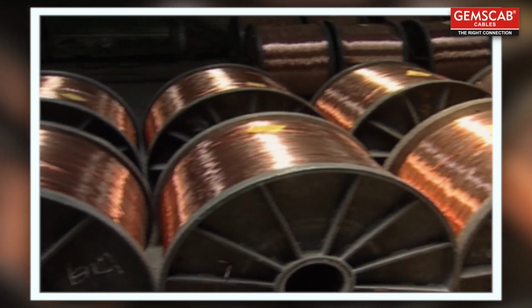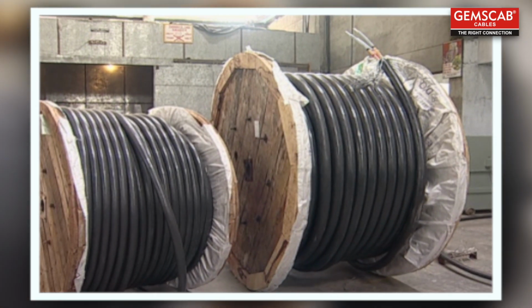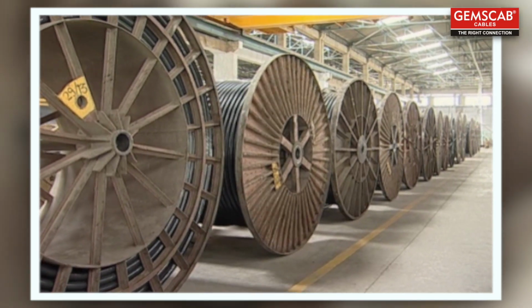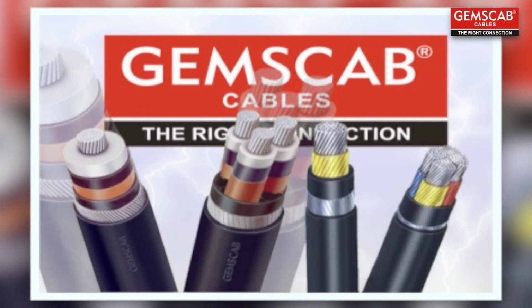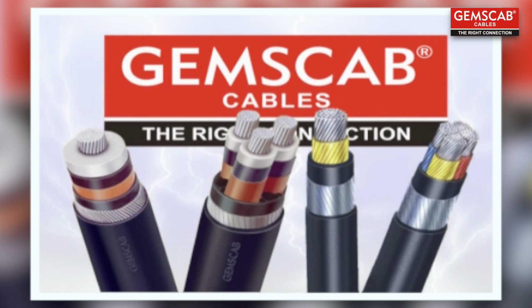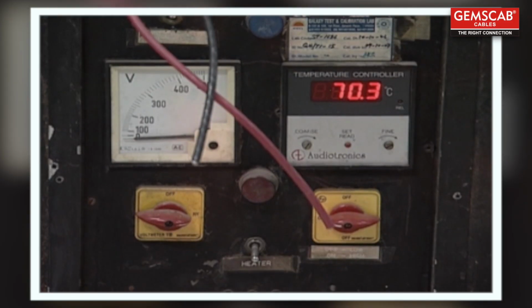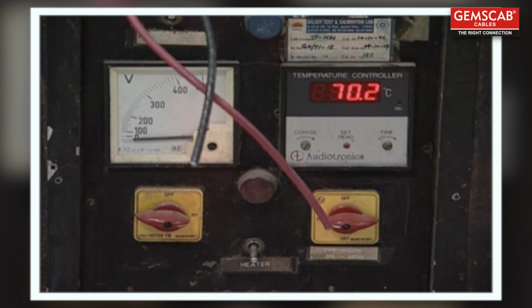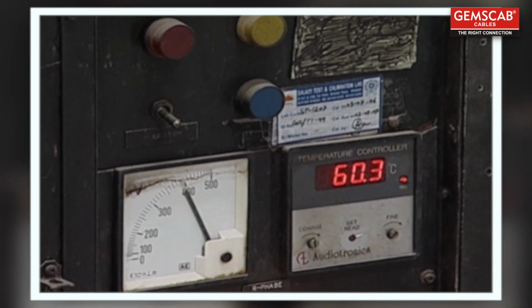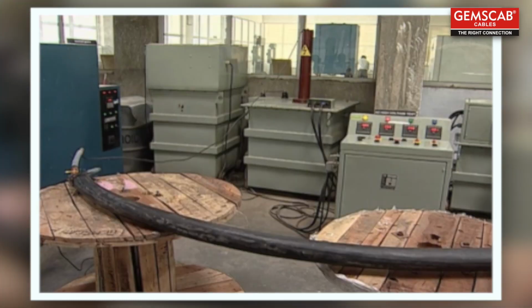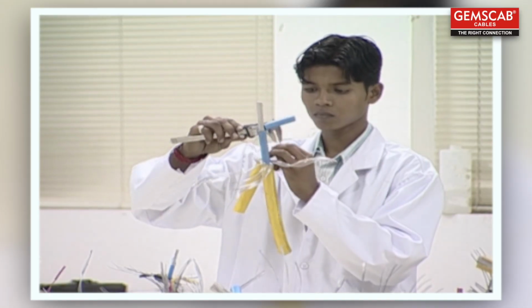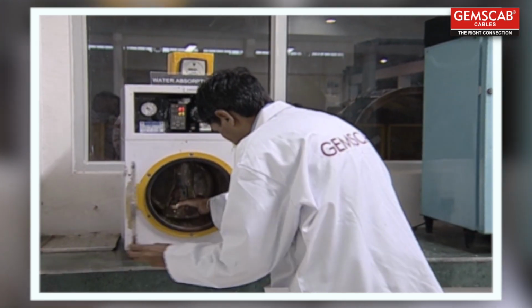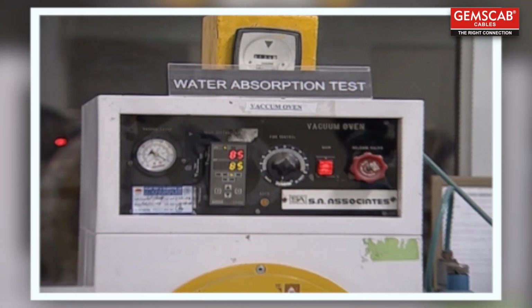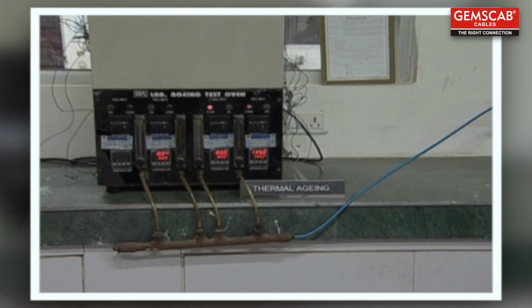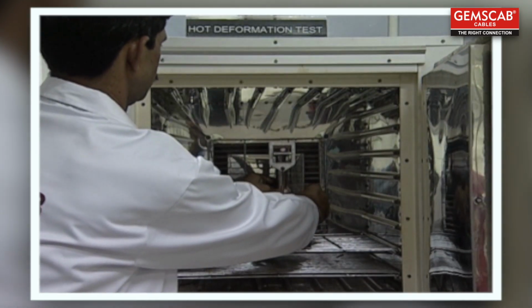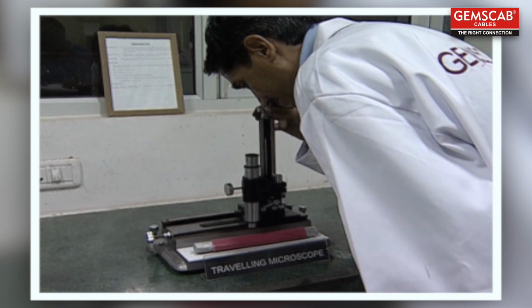Their excellent installation properties permit these cables to be used even under most difficult and cramped cable routing conditions. Both Gemscab LT and HT cables have higher conductor temperature rating, a higher emergency overload capacity, excellent insulation resistance, and a high maximum temperature limit under short-circuit conditions. They are resistant to corrosion, pollution, chemicals, and gases, and are better made to withstand vibrations and hot impacts, can be joined easily, and have low installation cost because of their dimensions and superior flexibility.